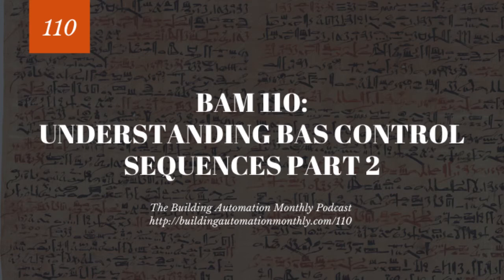I know this is a long little diatribe here, and I know you're expecting control sequences, and I promise you we will get to that. But do you see the problem with this logic? Do you see why you have to understand the bigger effect on the system? Because if you simply said, oh, 50 CFM, and then you had the outdoor air at 10-20% of damper for the mixed air unit, that would not be a true 50 CFM of outdoor air.